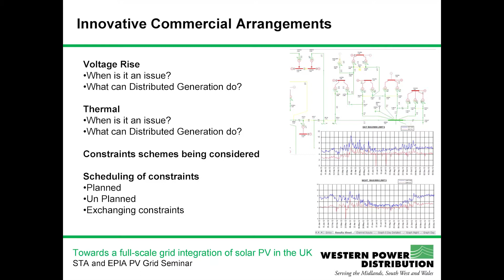Equally, it's credible. We also have to calculate to make sure that the voltage wouldn't exceed the maximum headroom, so we put the voltage at the maximum it could be operating at, and take certain n-1 scenarios. All 4 of them happening together are plausible scenarios that could happen over the life of a generation connection, which means we have to design our network, because it's passive, to those conditions. But because of all those things having to line up in time, it actually means that there is extra capacity in the network, which is available at times, just not every time.